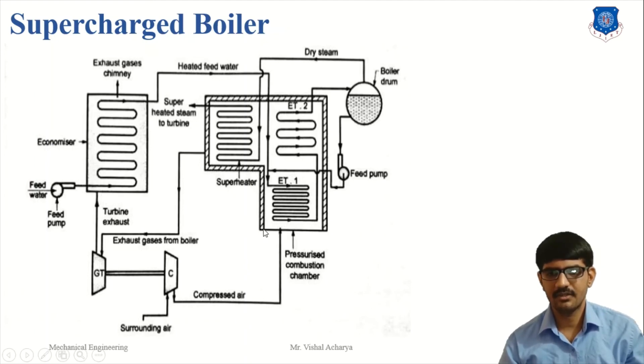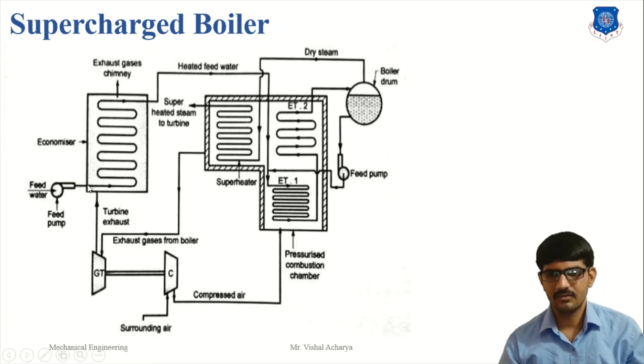The supercharged boiler: air is compressed by the compressor and supplied to the furnace where hot gas is produced. The hot gas then passes through and does work. The exhaust gases go to the economizer for water heating. Water is supplied into the economizer where temperature increases. From the economizer, water goes to the boiler tube where temperature increases further and is converted into saturated steam, then passed to the superheater and converted into superheated steam by the help of the gases.